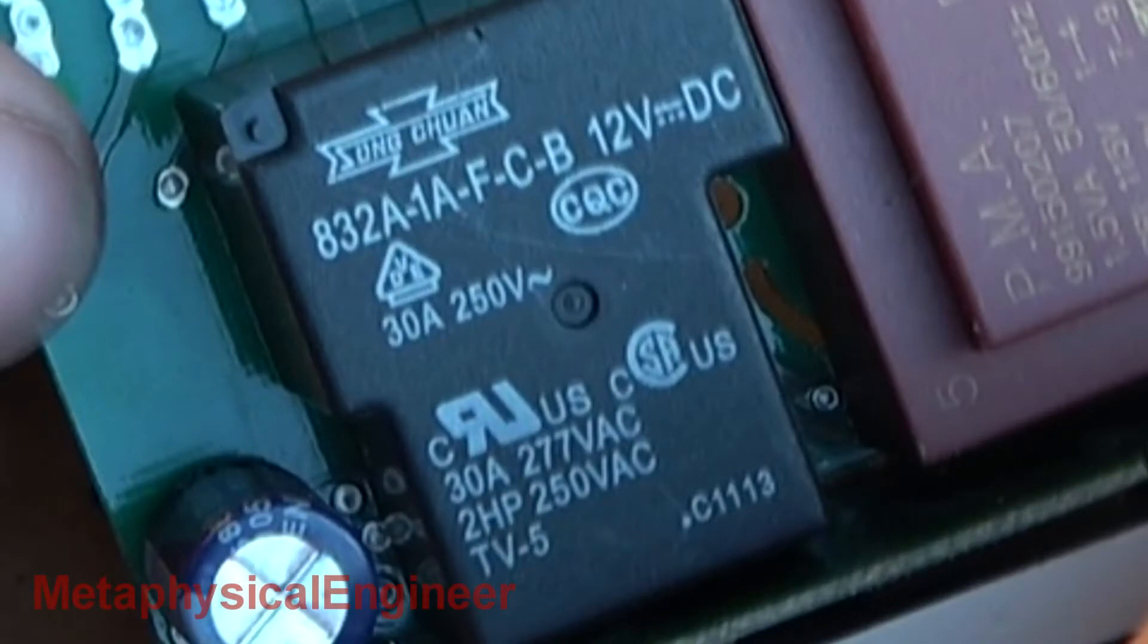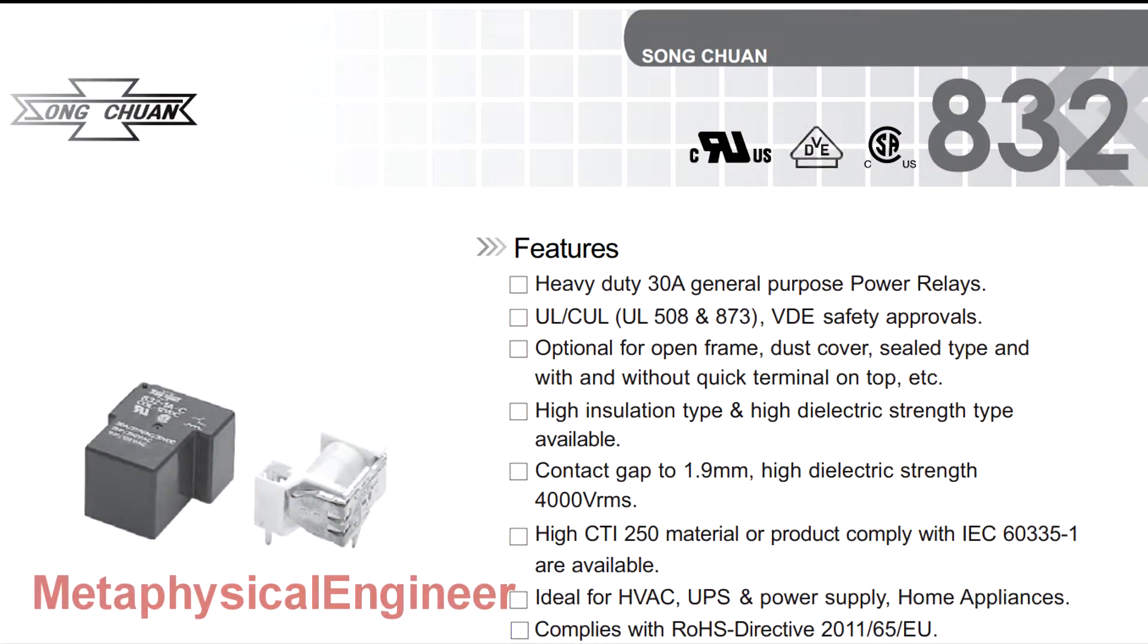Let's compare the specs of the relay to the conditions it faced. It wasn't running a very big cooler, with a compressor rated load amps of about 7, an inrush current in the 40 amp range. The relay claims to be a general purpose, heavy duty power relay in normally open, single pole layout, with suitability for HVAC applications.